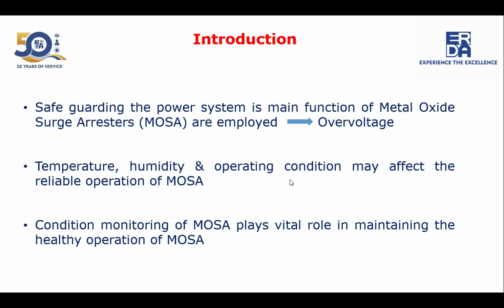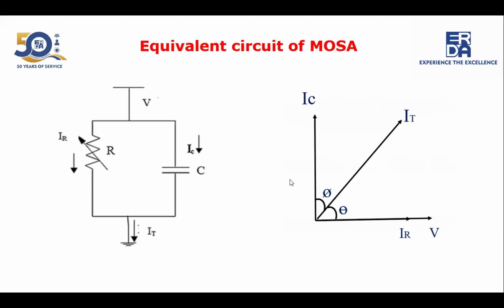Not only the MOSA but other equipment also, people perform some condition monitoring tests. When we talk about the surge arrestor, to verify the health of the MOSA we generally measure the leakage current. This leakage current is divided into two parts: the total leakage current, which is again bifurcated into the capacitive current as well as the resistive current.